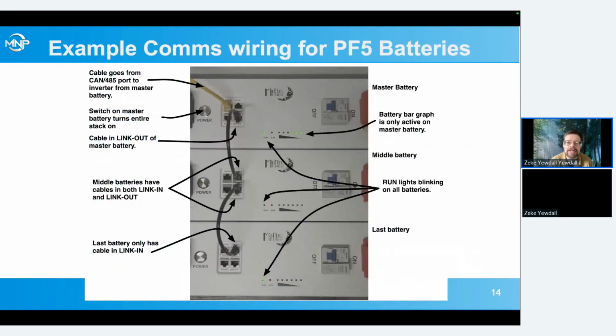Here's kind of showing what you see on a properly operating system. You see the cables going from the link in to the link out. These are the rack mount stack batteries, and it looks a little different on the wall mount batteries, but it's essentially the same methodology. You can see we've only got our bar graph active on the master battery up here, which has our CAN cable going off to the inverter.